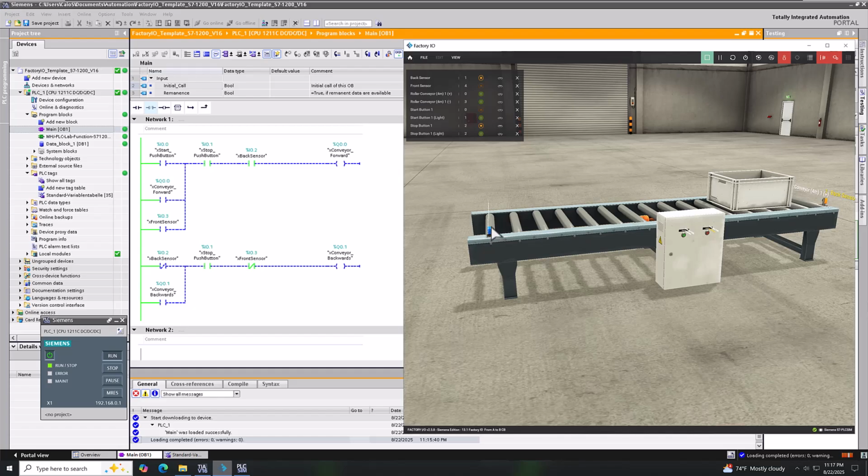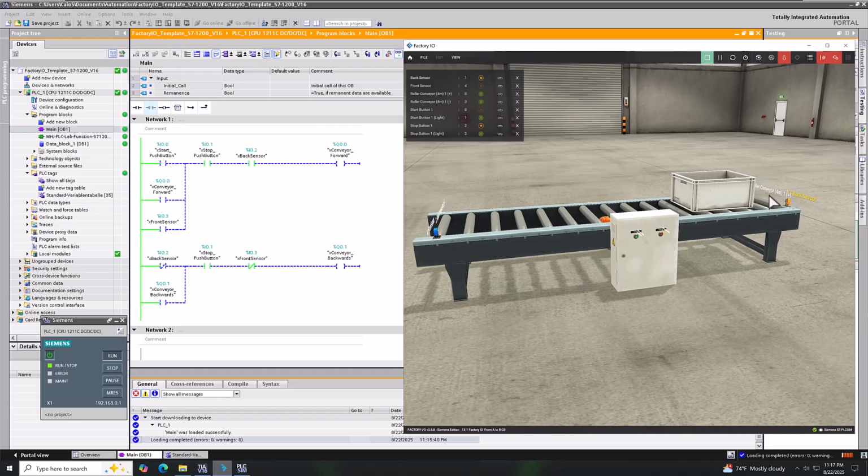I put a diffuse photo eye right here. So it's going to be made until the point where it's not made, and this is still the actual, let me get this out of the way so you can see it. This is still the photo eye that uses the reflector. So this is diffuse. Keep in mind it does not need a reflector when it's diffuse, and the other one is, like I said, a photo eye that needs a reflector to actually get its 1 or 0 command or 1 or 0 transition.